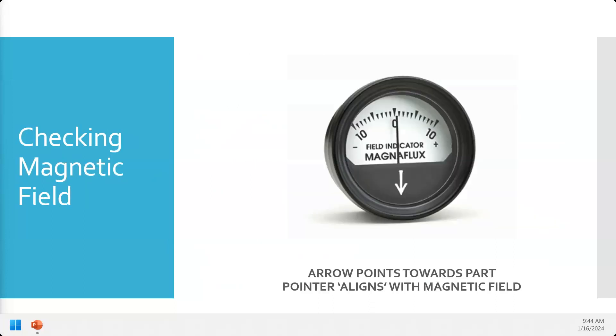Here is a Gauss gauge. You hold it in your hand — it's about the size of a compass — point the arrow towards the part, and move it around looking for maximum deflection. Ours show up to 10 Gauss positive and negative. As you move it one way through the field, the needle deflects to the positive side; bring it back through the field and it goes negative. We don't know which direction our field has formed — we just want to confirm a field has formed, so you wave it back and forth and note the reading.